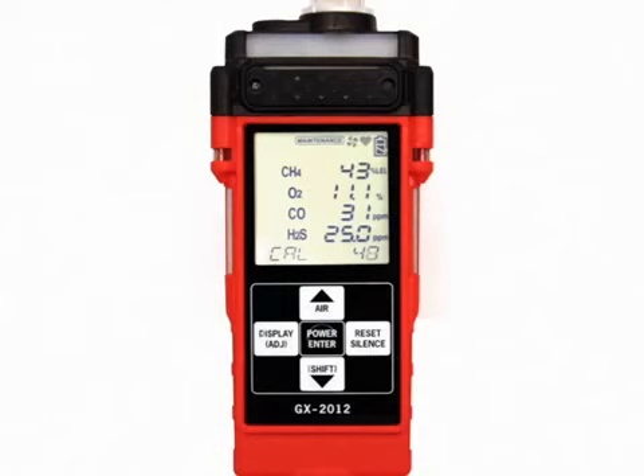When Auto Cal in the Bump Set menu in maintenance mode is set to on and any channel fails the bump test, the instrument will beep and a calibration is immediately and automatically started. Continue to apply the calibration gas. Cal on the bottom left of the screen will alternate with Apply. The calibration time will begin to count down in seconds in the lower right of the screen.